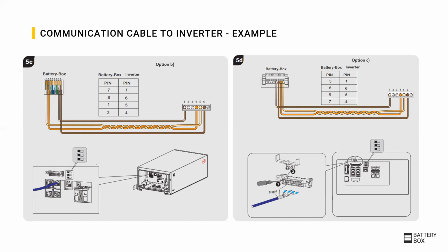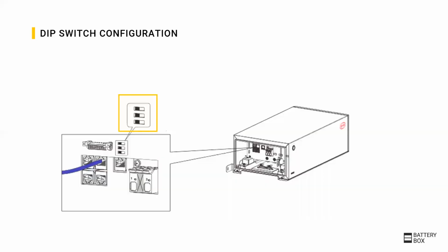If you face problems, test the cable or try another cable, or try the other connection option if available for the inverter. Besides the correct cabling, also dip switch configuration is important. Different inverters have a different dip switch setting, so please always make sure you are using the setting described in the manual. In this picture, all dip switches are on the left position, but this is different dependent on the inverter. A wrong dip switch configuration could again prevent the system from working, so please always check the correct position of the three switches.